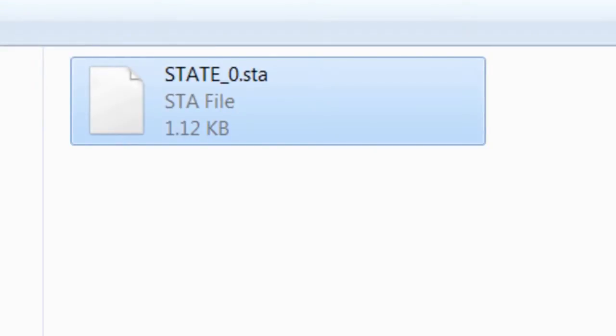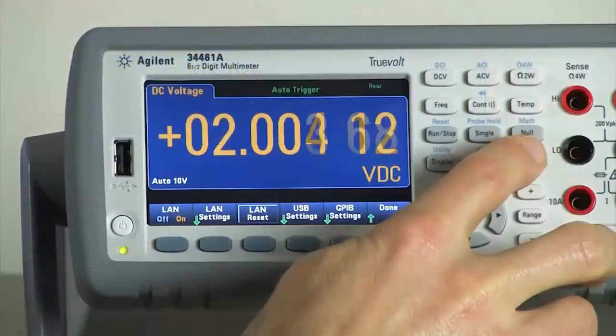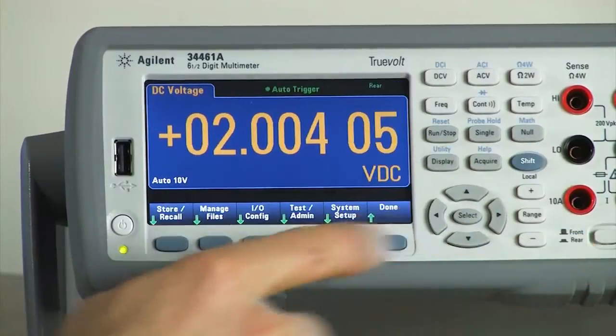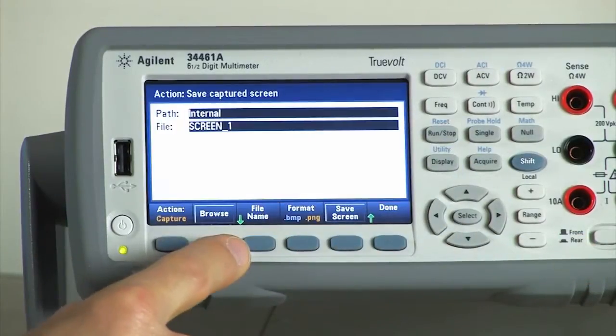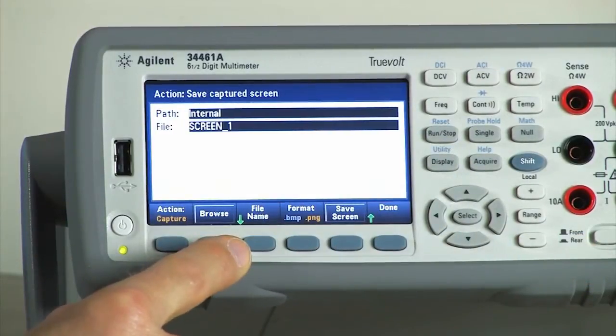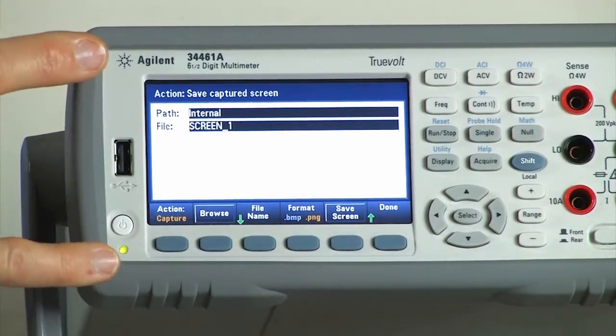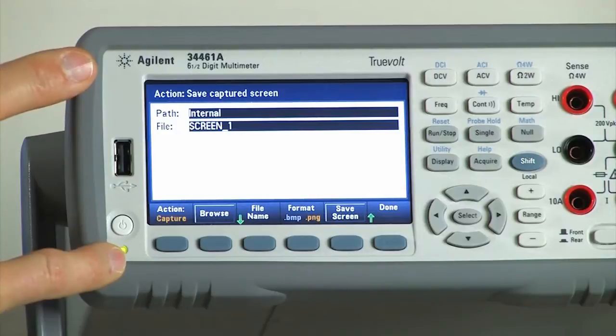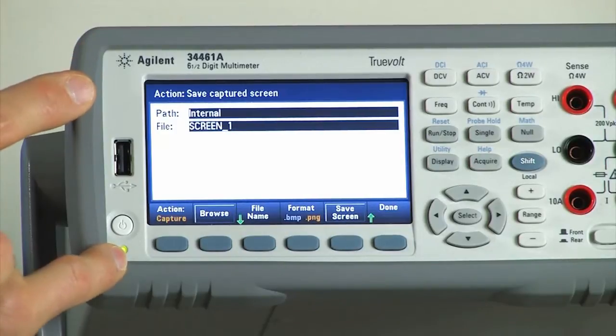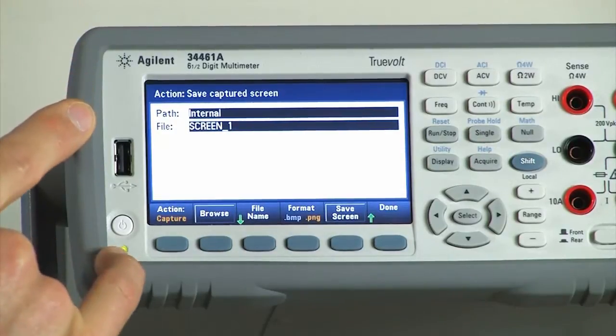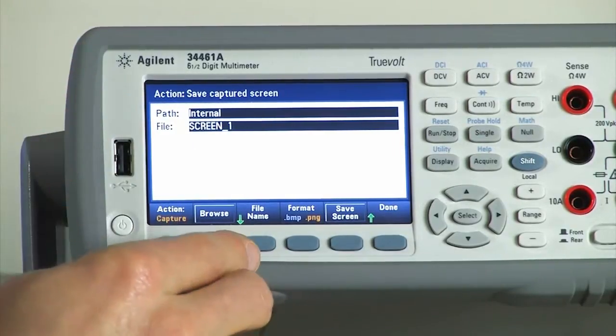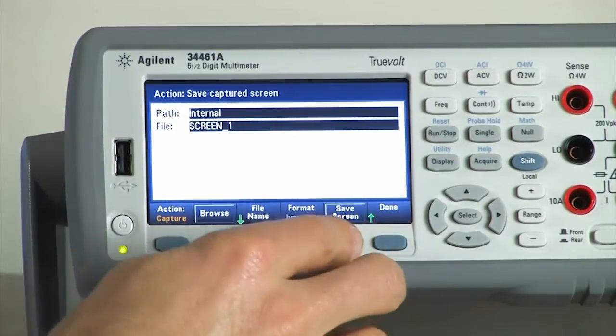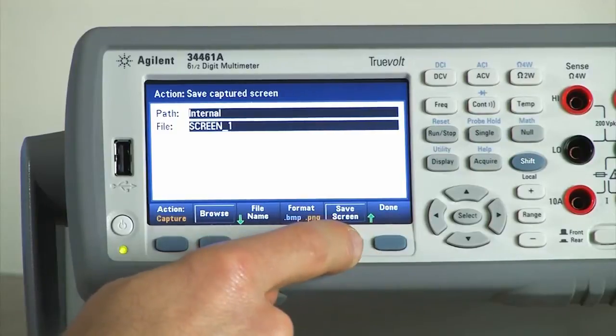The next thing I'd like to show is capturing a screenshot and transferring that to the PC or viewing that on the PC. So to do that, we do Shift-Utility, Manage Files. Then we'll get a pop-up screen that's pre-populated with a screen file name. We can change the file name or we can just click Save Screen.